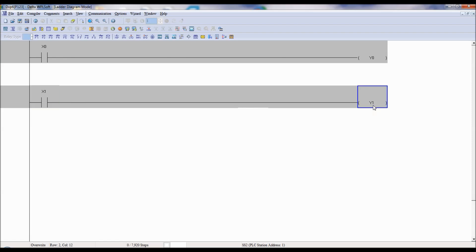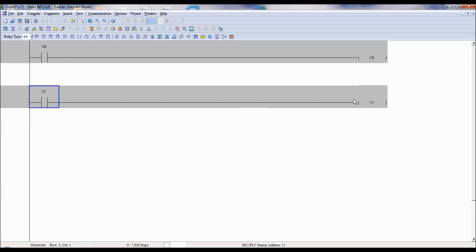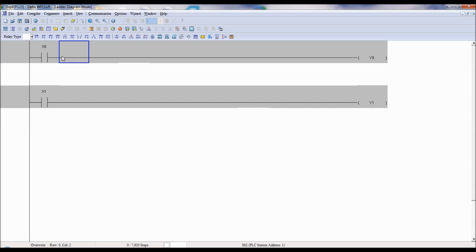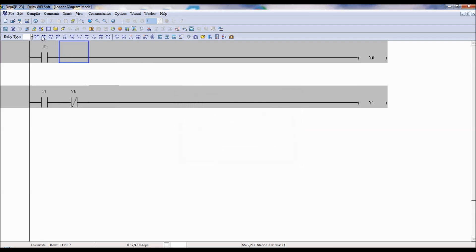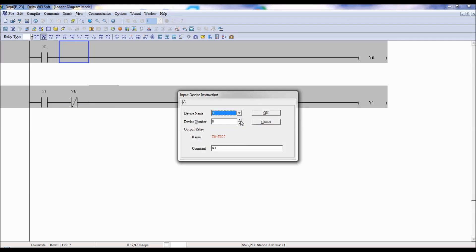But assume the user operates X0 as well as X1 at the same time — K1 and K2 should not be on simultaneously. That means a command for both forward and reverse is not acceptable. That is why there is a concept of interlocking. If Y0 is on, then Y1 should not be on. So I am using the normally closed contact of Y0 and the normally closed contact of Y1. This is the interlocking concept.